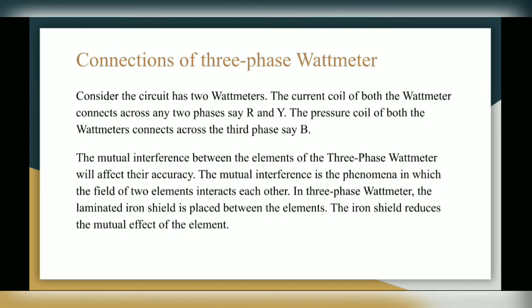So in this, there are two elements, so the magnetic fields of these two elements affect each other. To avoid this, the iron shield is placed in between these two elements. In this diagram you can see there are two elements. The first element is connected in the R phase, the second element is connected in the Y phase.